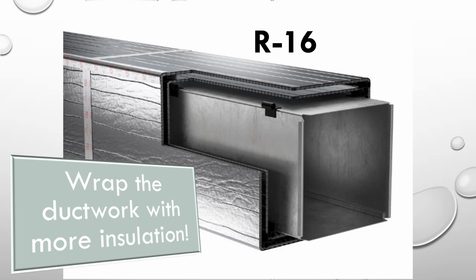All right, this one was a pretty good idea, I thought at the time, even though it was crazy. But we went ahead and wrapped the ductwork with double the amount of insulation, so we double wrapped this to form R16. It really didn't help us at all. For one thing, it's ridiculous because it looked like a pillow. You had 4 inches of thick insulation going both ways, so the ductwork looked massive. I mean, a lot of places you can't even fit ductwork like this. We just knew it wasn't a real solution, but because it was a crawl space at the time, we had the height to do this. But it still didn't fix the condensation issue.